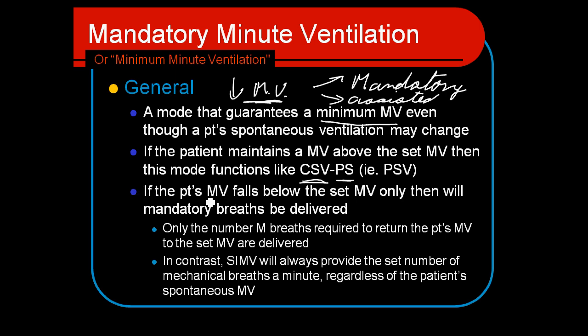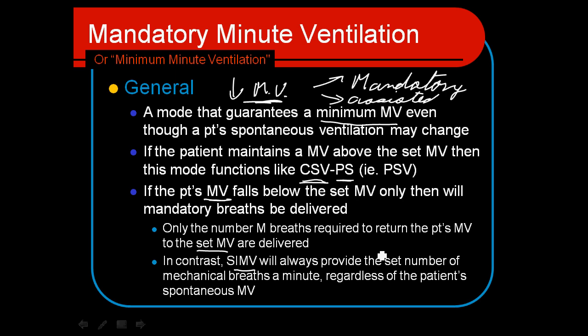If the patient falls below the minute ventilation established by the operator, the ventilator will kick in giving those mandatory and assisted breaths; otherwise it allows the patient to spontaneously breathe in pressure support mode. It will only give the number of mandatory breaths required to return the patient's minute ventilation to the set minute ventilation. So if they drop down just a little but are still spontaneously breathing, it'll kick in with an IMV breath to augment their minute ventilation and boost them above that goal.